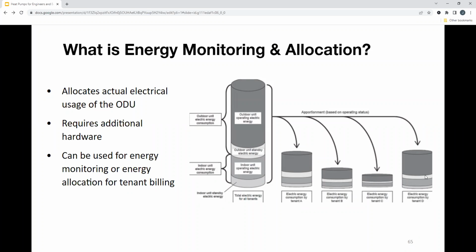And then in some states, you can actually do billing purposes. But right now, I want to show you this because if you are looking to monitor part load efficiency, this is a great option to do that. Right now, as far as energy allocation goes for tenant billing, New York City does this and a couple other states do. However, most manufacturers, all the manufacturers in the Massachusetts area have not been approved for this. It's actually getting revoted on in September. It's the Act relative to energy conservation. It's 3361. And basically what that does is approves manufacturers' algorithm for calculating the kilowatts used over a month span. That can be used for tenant billing.